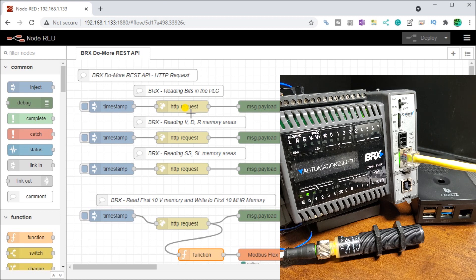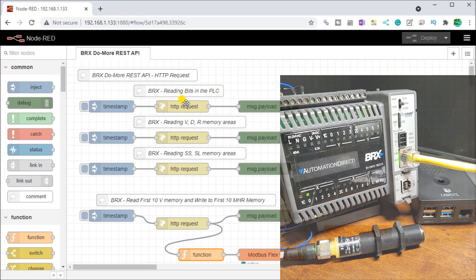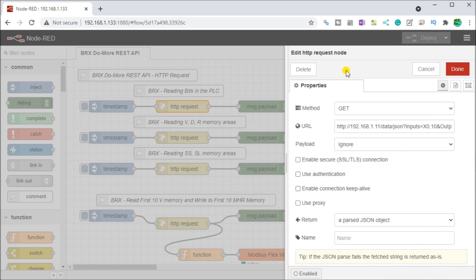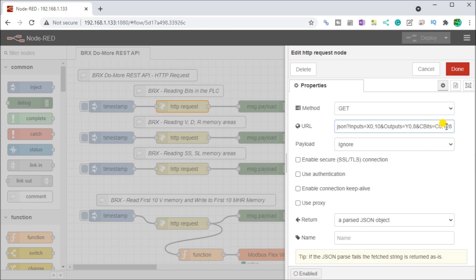You will see that the HTTP request node is installed automatically when we install node red. We have a timestamp here. We'll read the bits in the PLC. Then we go to a payload. Our message request, if I double click it, you can see that I'm asking for inputs X zero and I'm asking for 10 of them. I'm also asking for my outputs Y zero and I'm asking for eight of them. I'm also asking for C bits, C zero and I'm asking for 128 of them.